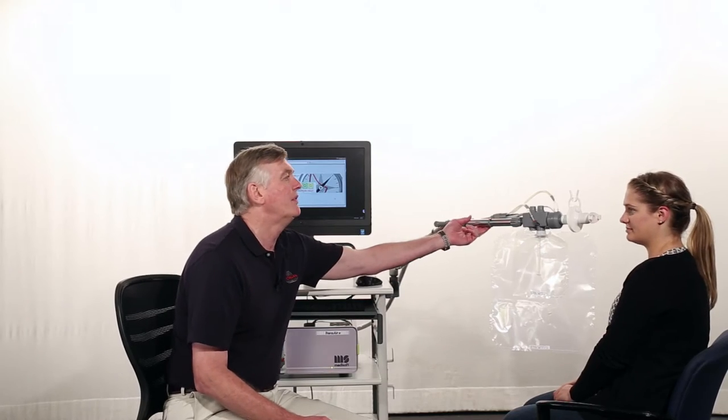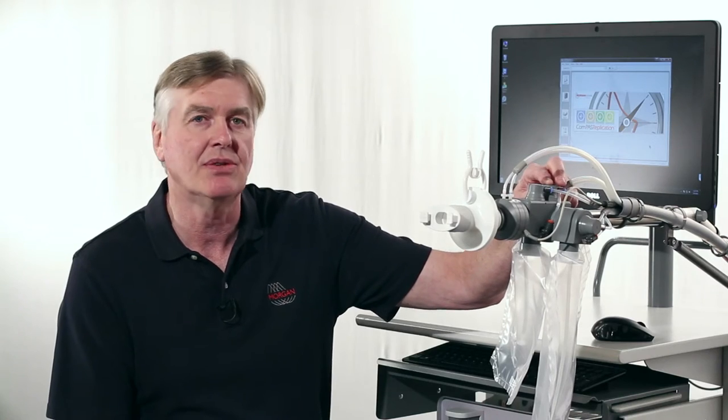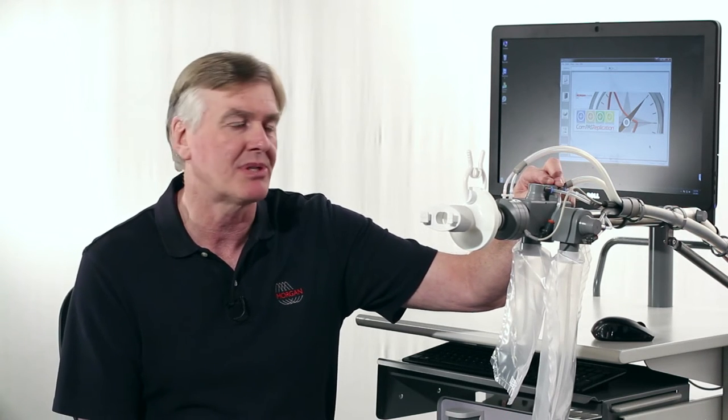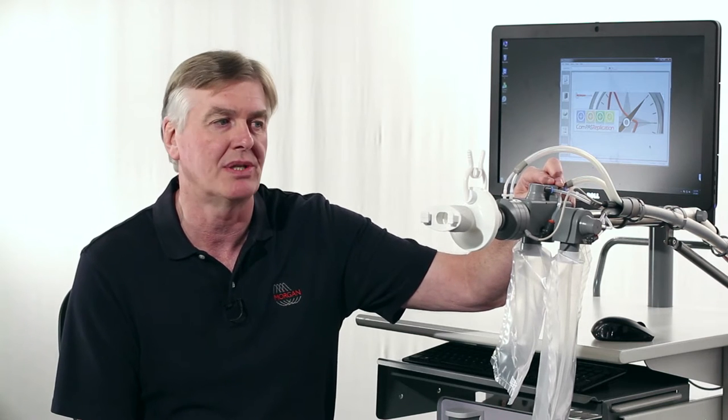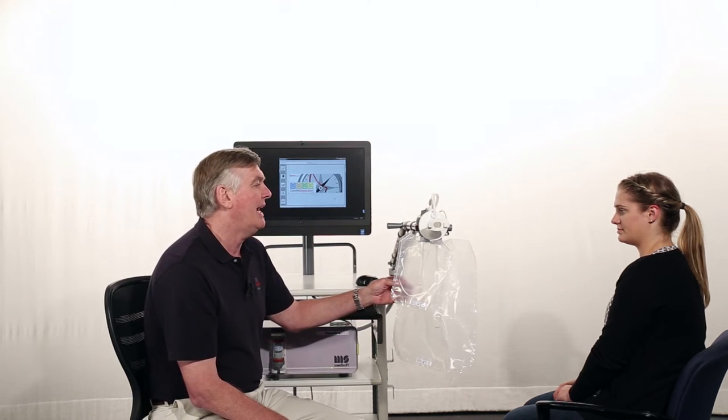The valve, the patient valve here, is all driven by a single cylinder of diffusion gas. It's pneumatic, requires absolutely no service maintenance whatsoever. The other feature you'll see underneath the valve are what we affectionately call our ugly bags. These are used for the measure of single breath diffusion and are key ingredients to obtaining reproducible and reliable diffusion results on small children and very sick adults.